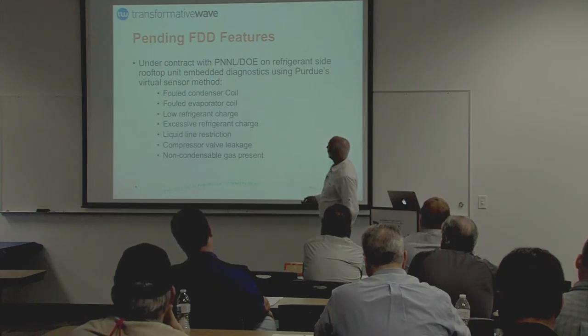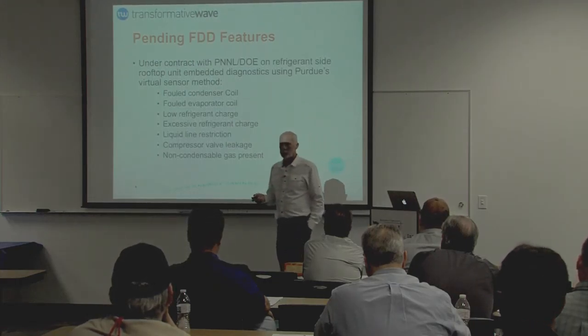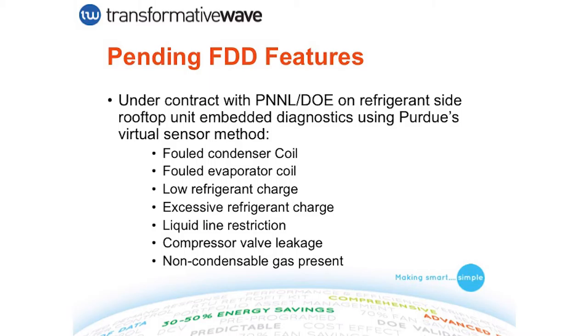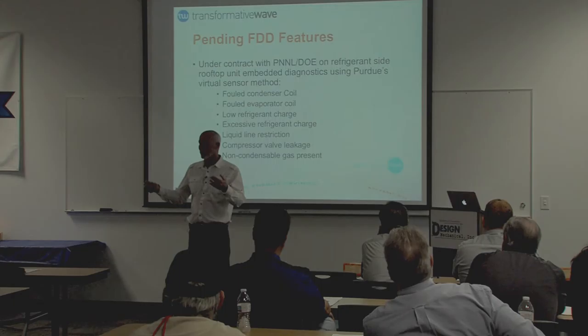But what's this about? Well, this is refrigeration side fault detection. Most of our fault detection focuses on the air side and the economizer side. If there's a fundamental cooling problem, we can tell seven different things through the use of just temperature sensors.